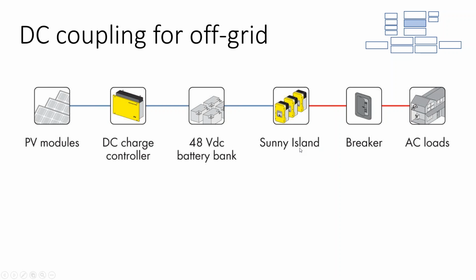So in short, DC coupling is the better solution for off-grid new construction. AC coupling is the better solution for utility scale plants, commercial batteries, or even residential backup batteries. And don't sweat it if you're retrofitting and already have a solar array with an inverter — AC coupling will still get you there when trying to take a home with an existing solar array completely off grid. AC coupling is a good path forward; you don't need to throw everything out and start over.